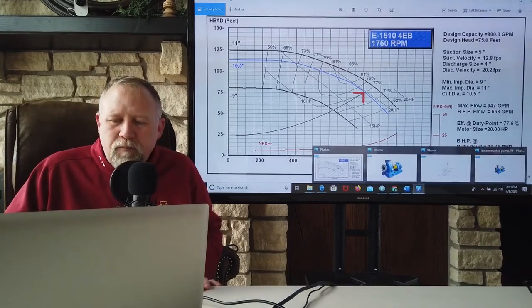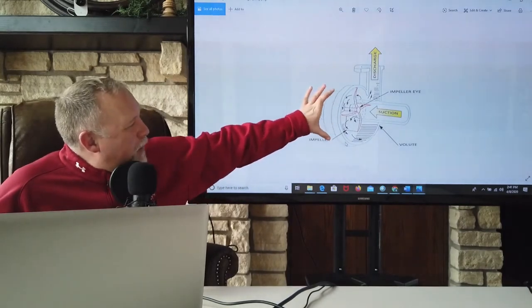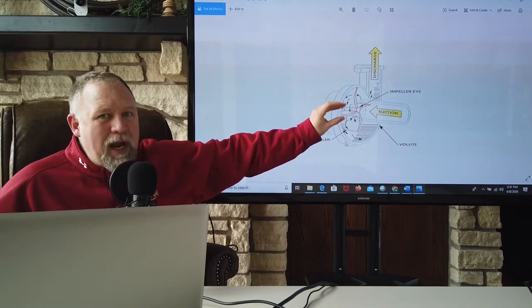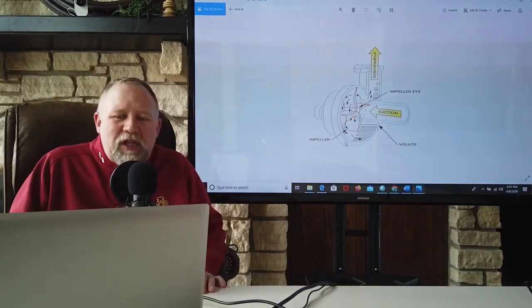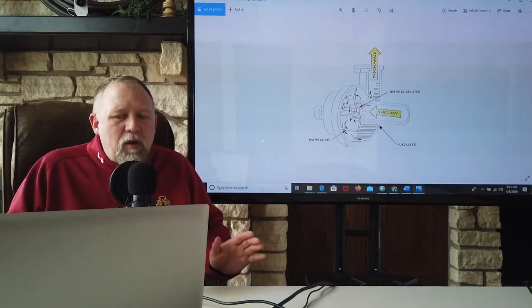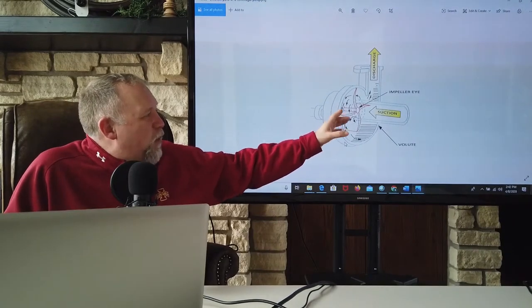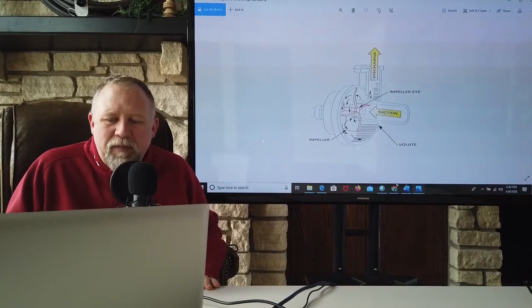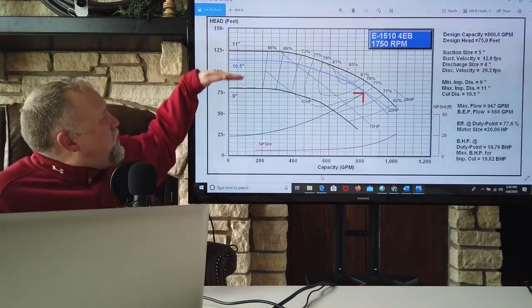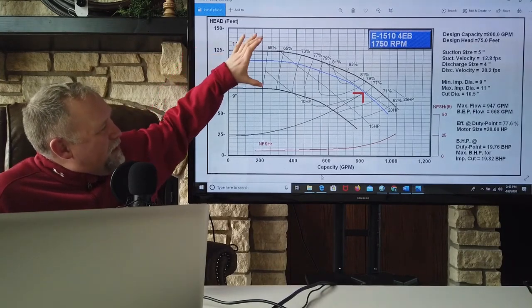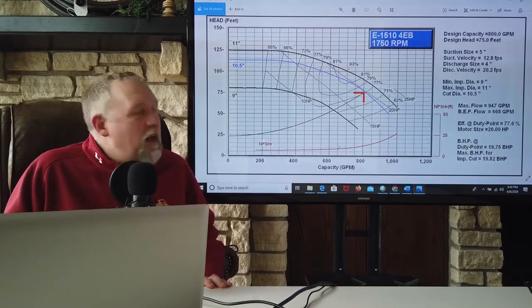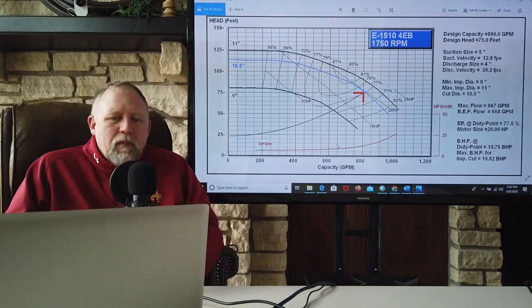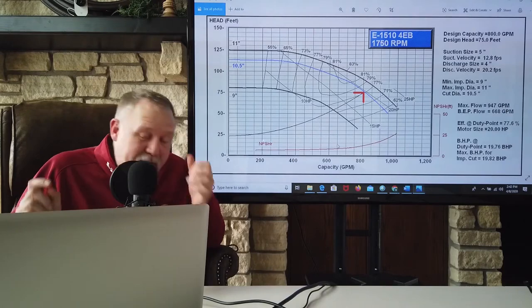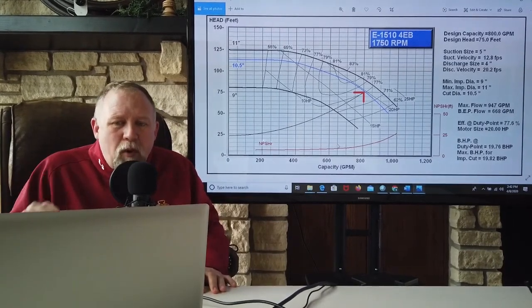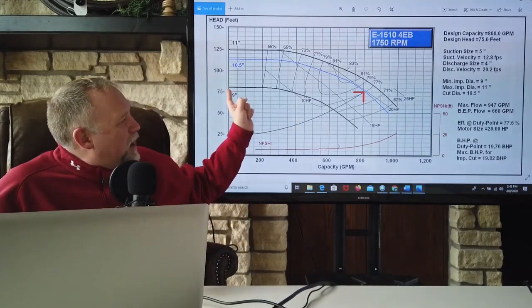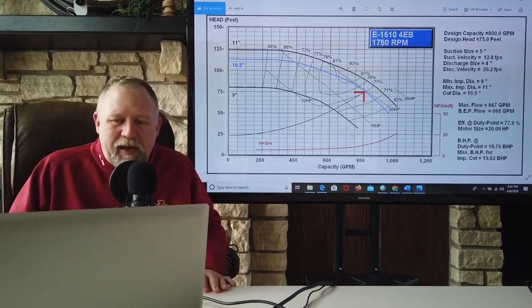Like if we go back to this, for a given pump case size, we could put a range of impeller diameters in here. You don't just have one casing size and one impeller size. We could get a 9-inch impeller, 9.5, a 10, whatever. We could get a wide range of impeller sizes. So think of this diagram as from 9-inch to 11-inch impeller for this particular pump casing. And notice, it is at 1,750 revolutions per minute. At that combination of impeller, pump case, and motor speed, these are all the possible combinations of flow and pressure that particular pump can generate.